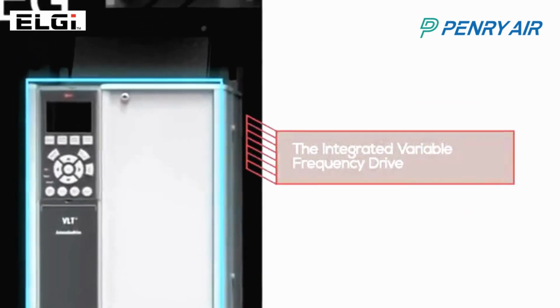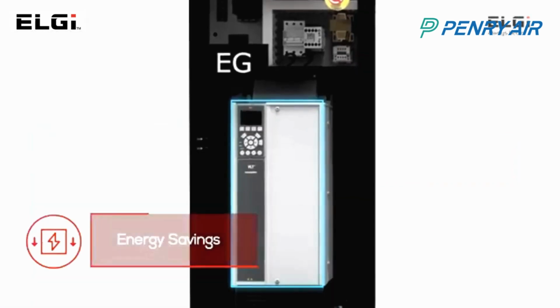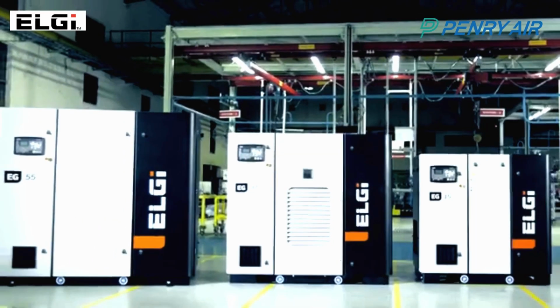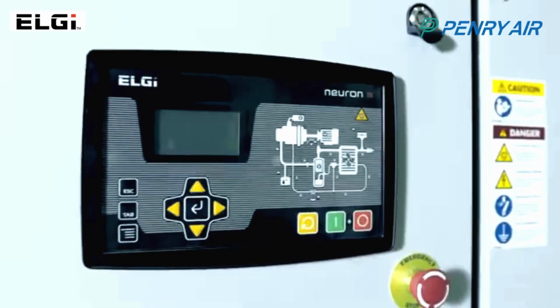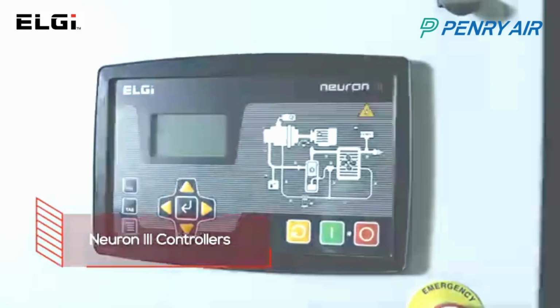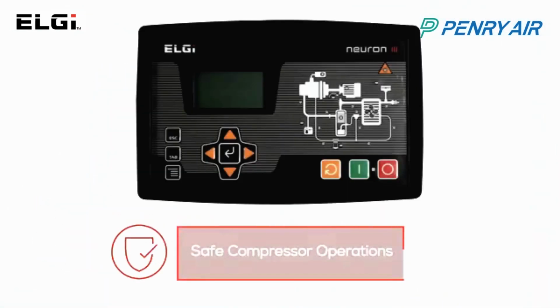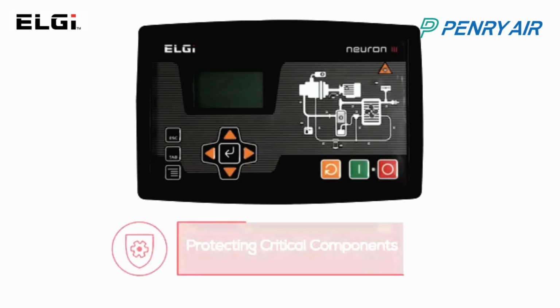The integrated variable frequency drive offers significant energy savings by varying the flow with the actual demand of the application. The EG series of compressors are equipped with advanced yet easy-to-use Neuron 3 controllers. The controller ensures safe compressor operation, providing protection against major failures and ensuring safety for critical components. Additionally, the controller allows remote operation through Modbus.